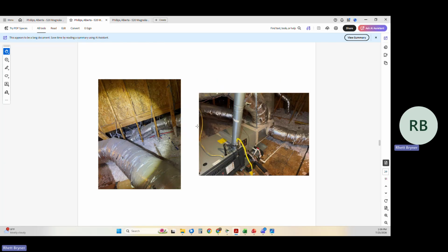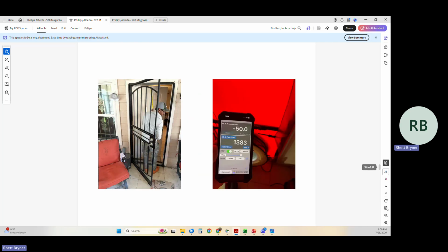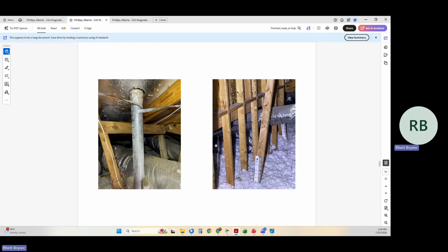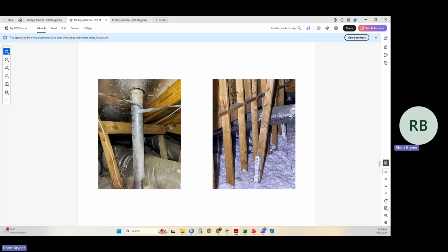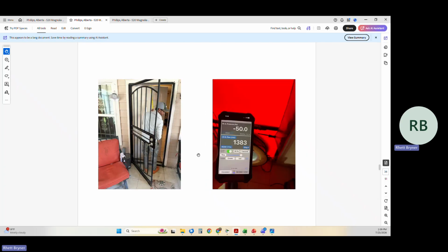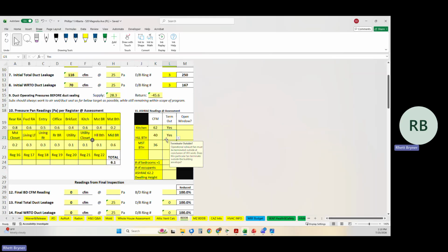Hard to see here, but I think I took a photo later, actually. There you go. So there's actually some pipes off in the corners, sort of hidden a little bit behind the rafters and joists. But they actually do vent to the outside. You can also tell this by looking at the exterior to see how many vent pipes you have on the outside. So in this case, both of these did terminate outside.